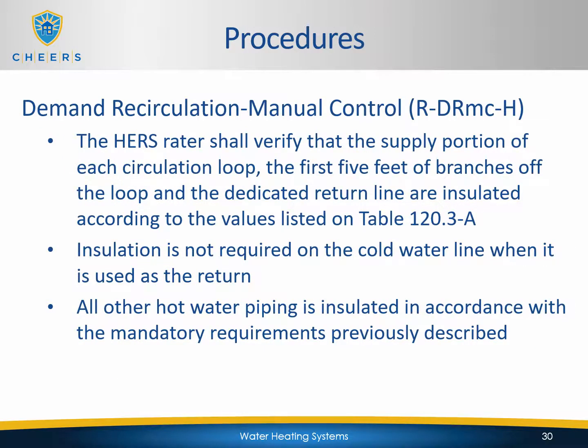The HERS rater shall verify that the supply portion of each circulation loop, the first 5 feet of branches off the loop, and the dedicated return line are insulated according to the values listed on Table 120.3-A. And again, that's the table that we previously looked at in the pipe insulation section. Insulation is not required on the cold water line when it is used as the return, and all other hot water piping is insulated in accordance with the mandatory requirements that we previously described.